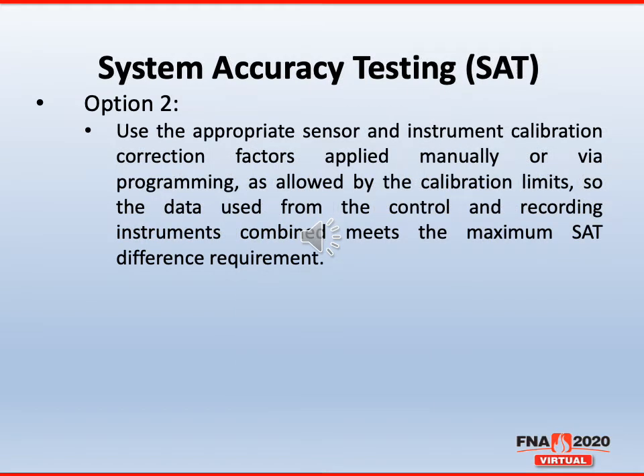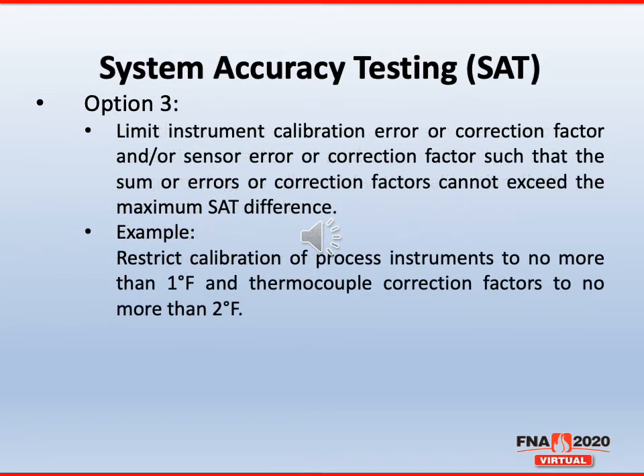Option 2, use the appropriate sensor and instrument calibration correction factors when applied manually or via programming, as allowed by the calibration limits of AMS 2750. So when the data used from the control and recording instruments are combined, they meet the maximum SAT difference. And option 3, limit your instrument calibration error correction factors and/or the sensor error or correction factors so that the sum of the errors or correction factors cannot exceed the maximum SAT difference.